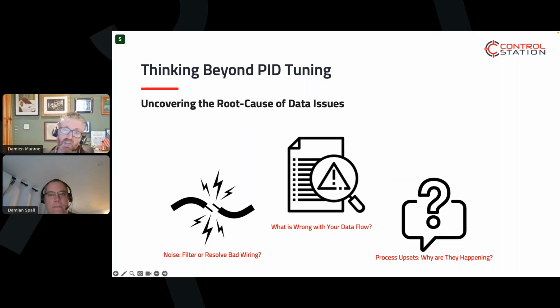Regarding noise and filtering, I regularly get asked: what kind of filter can I add? How do I filter out that data? Your filter needs to be very high frequency in reality - higher than your PID scan frequency - so it cleans out the high frequency noisy signals. That's where the only real benefit is. You want to remove that instrument and electrical noise.